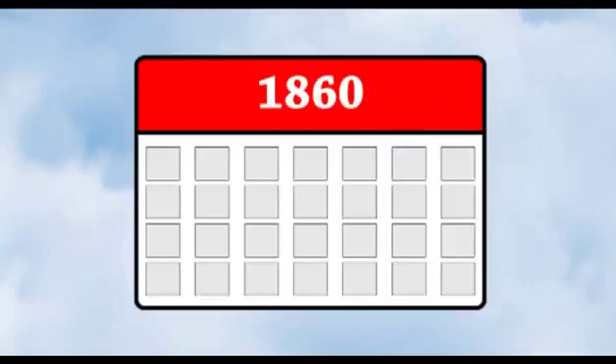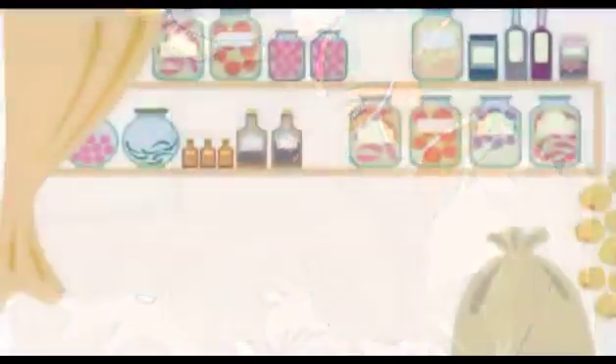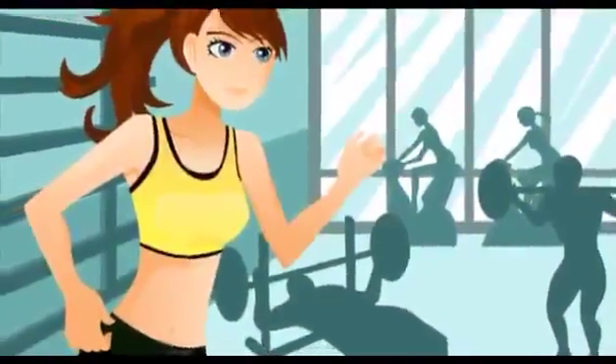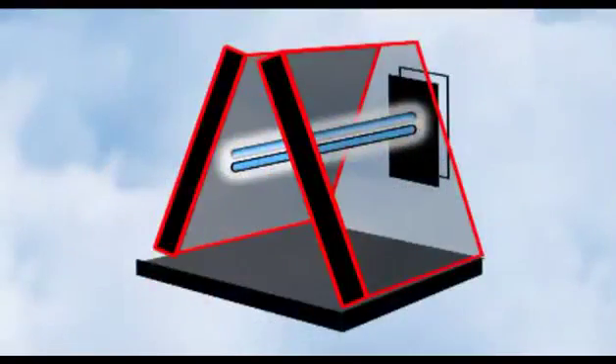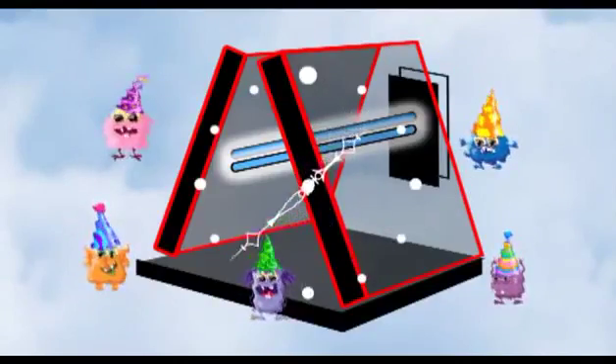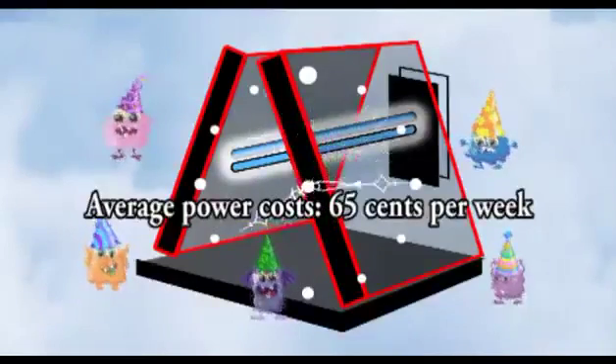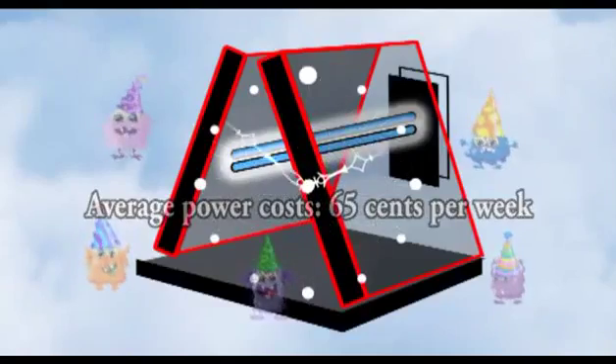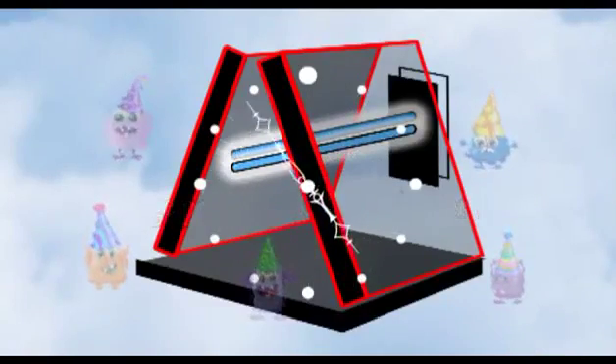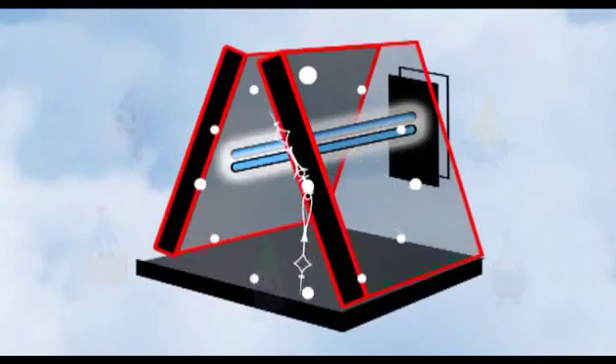These lights have been used for decades to fight disease and infection in hospital operating rooms, food storage areas, and wellness centers. The UVC Max 36 consists of a special power supply that is mounted on the outside of your air ducts or furnace while the bulb projects into the air stream. The light is on 24 hours a day to sanitize the air. If mounted near the cooling coils, it can actually help prevent the coils from becoming a biological breeding ground that results in a buildup of microbial matter that can block airflow through the coils, thereby increasing the overall efficiency of the system.